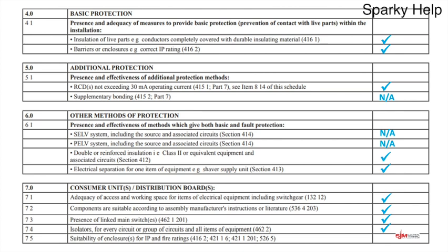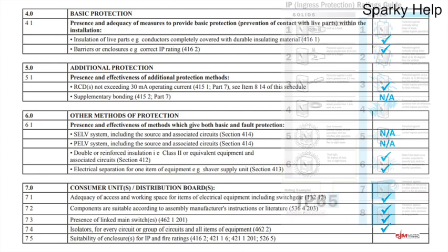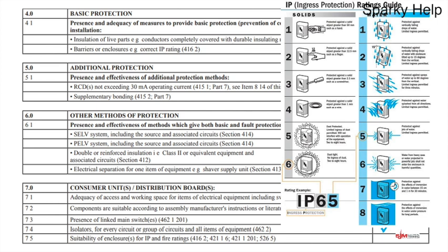If it's not, then it will be incorrect. Fire ratings, obviously making sure that it is metal and things like that. So here's the IP ratings that we tend to go by, and manufacturers make things too, so they might generically classify something IP 54. First letters is just ingress protection. The first number is all about solids, the second number is about water.